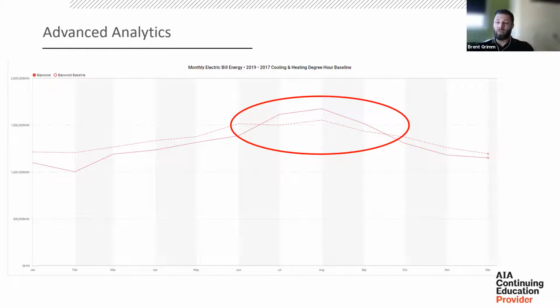When we pull this up, we're able to quickly see where some anomalies occur. We can see going from January to June, our 2019 usage is well below the baseline usage of 2017. But then in July, we have a big spike where we actually end up going above the baseline and we're using more energy than we were previously. One of the other things to note about this, and one of the great parts about the analytics, is we are normalizing for weather in this trend. So we can't just attribute this to maybe just a hot summer. If anybody's familiar with the Arizona climate out here where we are, those hot summers can be brutal.